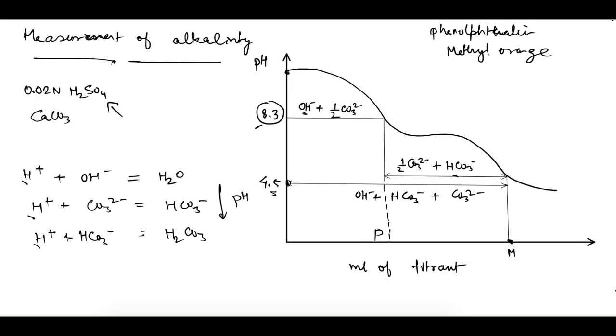As we add hydrogen ions and the pH reaches 8.3, it has been observed that all the hydroxide ions and half of the carbonate ions are neutralized. Only half the carbonate ion is neutralized because first the carbonate ion converts into bicarbonate ion, and then further acid is required. So we assume that half of the carbonate ion is neutralized at pH 8.3.